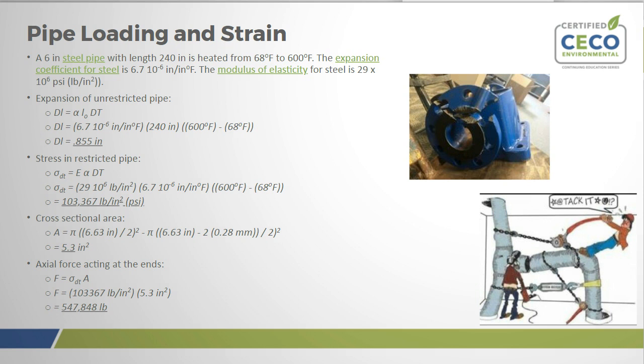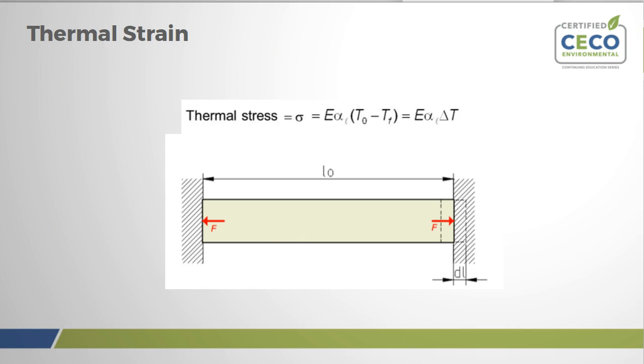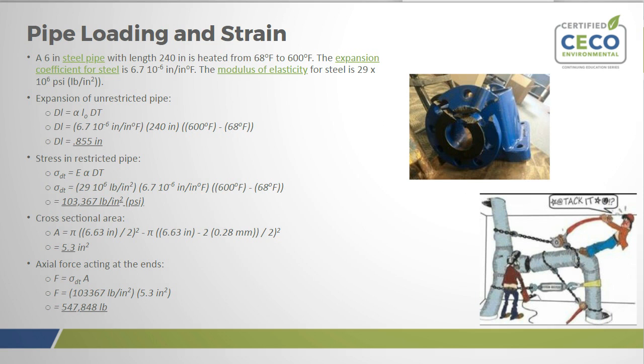So if you look back at this problem and then restrict that pipe, restricting that expansion, the stress in that pipe goes over 100,000 PSI. It's just a tremendous amount of force that is generated in the restricted pipe. Given the cross-sectional area of the pipe, we can resolve it down to a point force of nearly 500,000 pounds of force that can be exerted on the end of the restricted pipe.